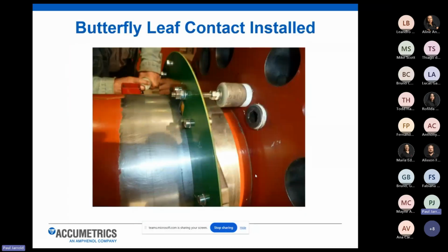That's what it looks like installed on the customer's machine. So you can see our electrical connection that goes down through the coupling flange of the exciter and connects to the backside of those butterfly leaf assemblies where the field voltage windings are, and comes and sticks out on this end to connect directly to our rotating transmitter. So the customer's exciter shaft does need to be clean and free of any paint or rust or debris, so we have a good, strong mechanical and electrical connection to the shaft itself.